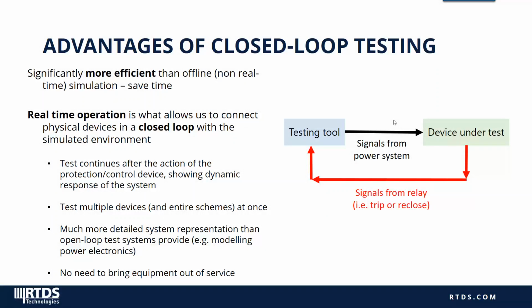Simulating a single fault might not be so onerous, but when you're running longer simulations, including slower acting dynamics and control, or running high volumes of simulations, the simulation time may become daunting using an offline tool, and running in real time can be tens or hundreds of times faster for complex networks. Okay, the other main advantage of running simulations in real time is the ability to connect external hardware to the simulation in order to test it in a closed loop.